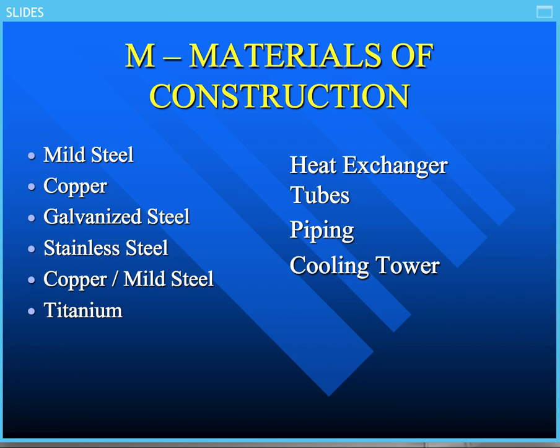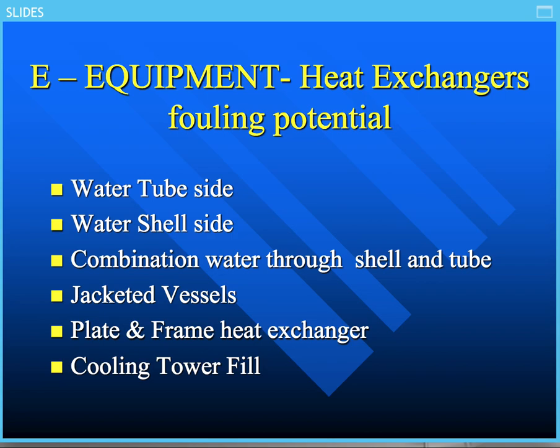Now we need to get to the next one, and that is the E. The E stands for, of course, the equipment. It's the design of the equipment. The equipment, is it you got water going through the tubes, or do we have water going from the shell side? The shell side is terrible in most cases because the velocities are low, there's fouling tendencies, etc. So that means that you would say, I'd have to have a much greater amount of dispersion in my treatment program to be able to handle that fouling condition. That would be a place for biological growth, so you need some better biological control.